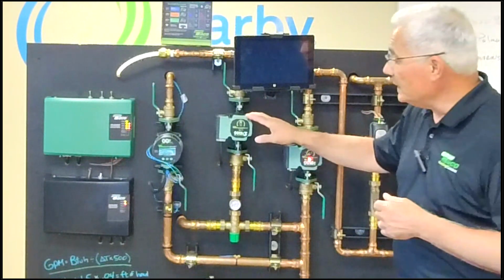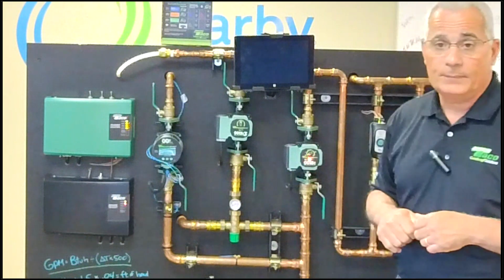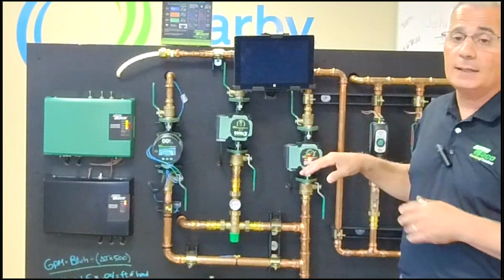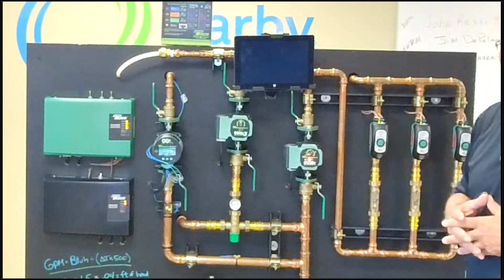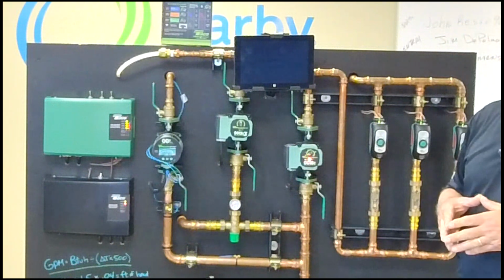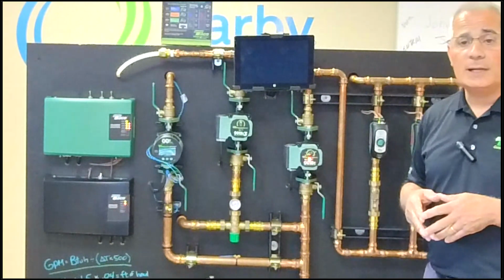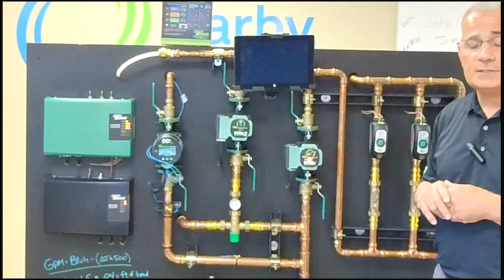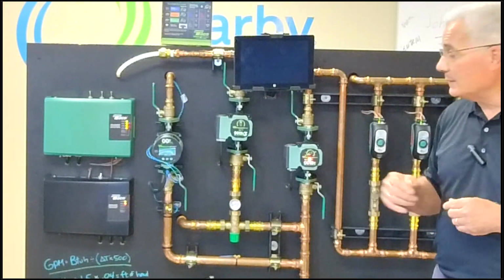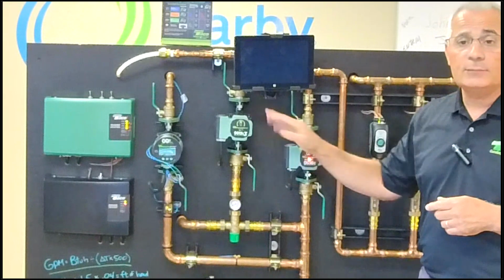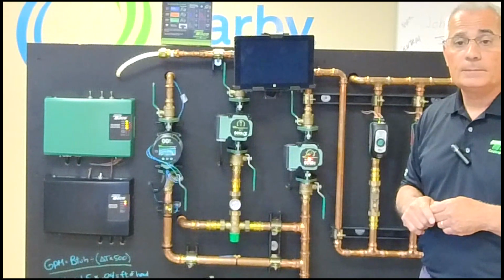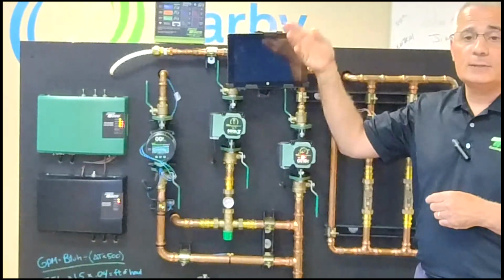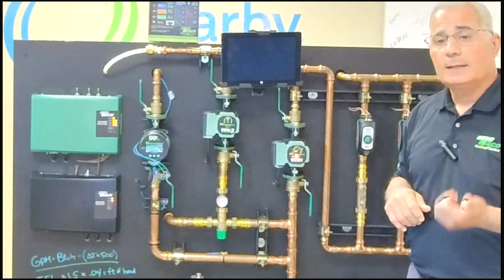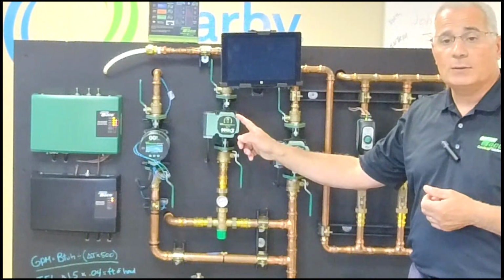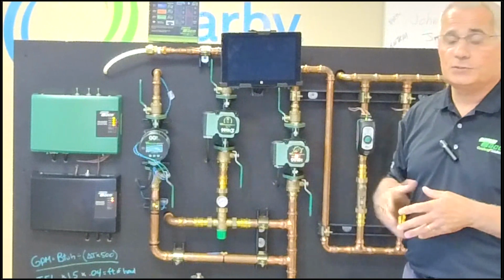So we have this circulator wired to an SR panel. Now I have a bunch of circulators on here, so we're using one larger SR panel. But if this was a typical job where I've got my 3 zones of space heating and I did add this radiant zone, this will be a single switching relay running this circulator. So my thermostat would come to that single switching relay. We would energize this pump when we get a call, and we'd send our end switch to our boiler.